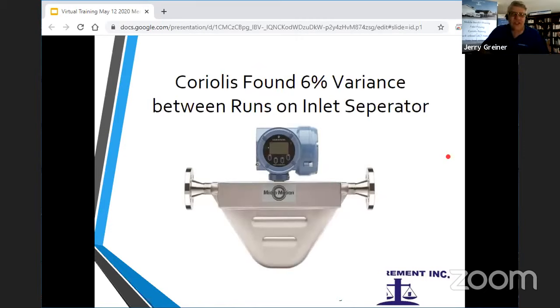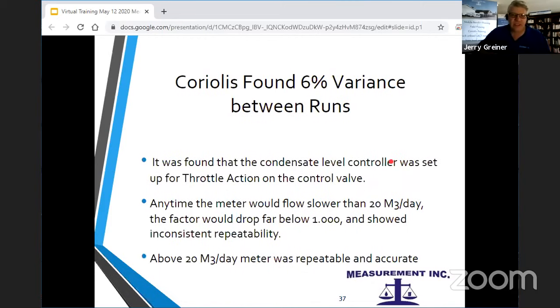Okay, another one, Coriolis. There was about 6% variance between runs on an inlet separator. This is an F series 1-inch meter it was on, and we found that the level control was on this type of meter. We found that it was set up for throttling action on a control valve, and anytime the flow would go slower than around 20 cubes a day, the factor would drop way below 1, and it showed very inconsistent repeatability. When it was flowing above 20 cubes a day, it was accurate and repeatable.